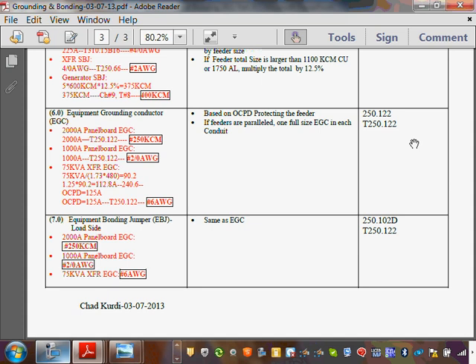Can you guys see that? Same as equipment grounding conductor. So the size is going to be too. So that equipment bonding jumper load side is exactly the same as the equipment grounding conductor. That's why what we do typically, guys, is you bring one of them inside the conduit, tie the conduit to it, the same wire, and go to the ground. So you bond the conduit and you ground the system in the same wire with bonding bushing.